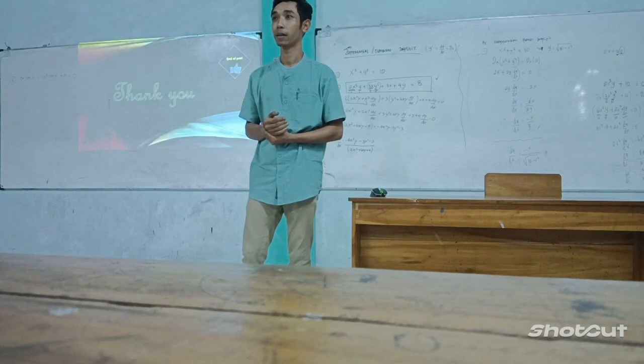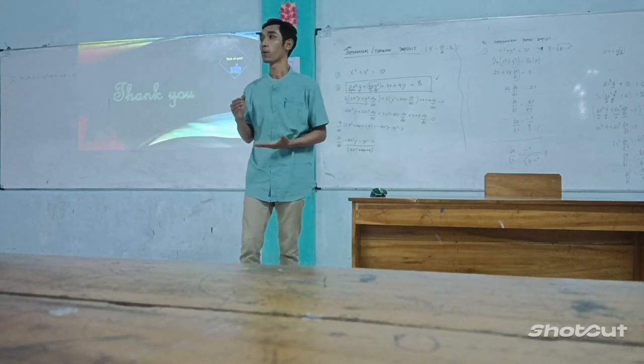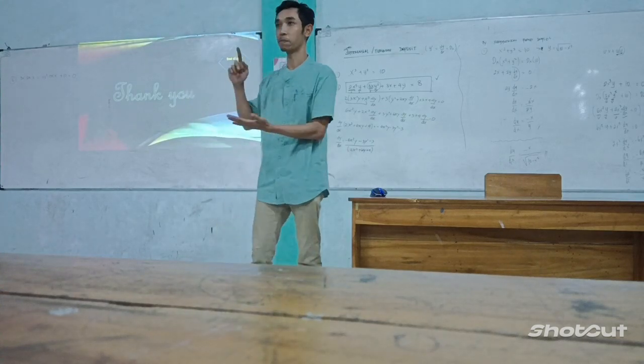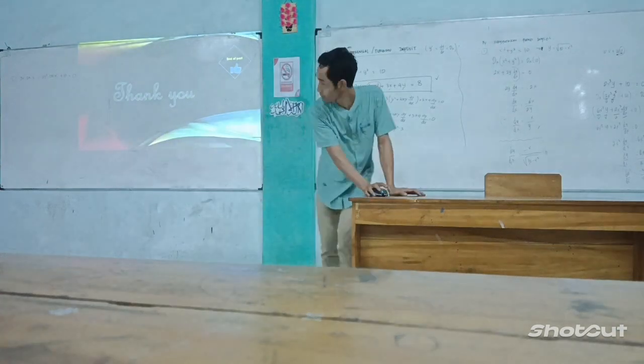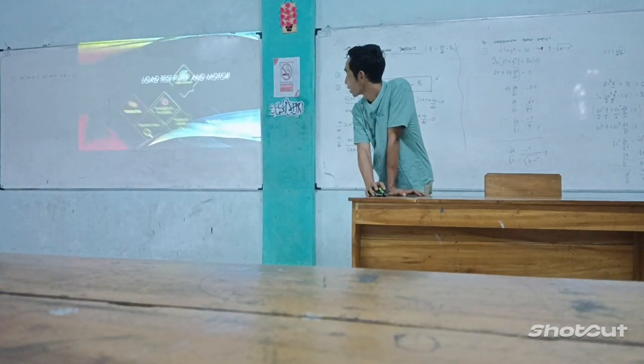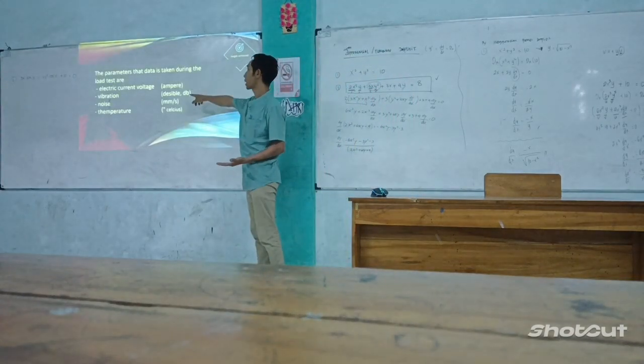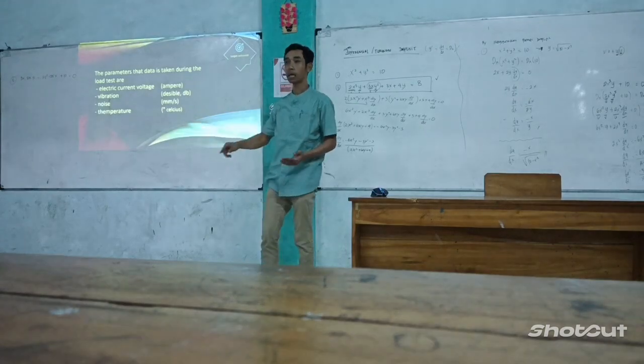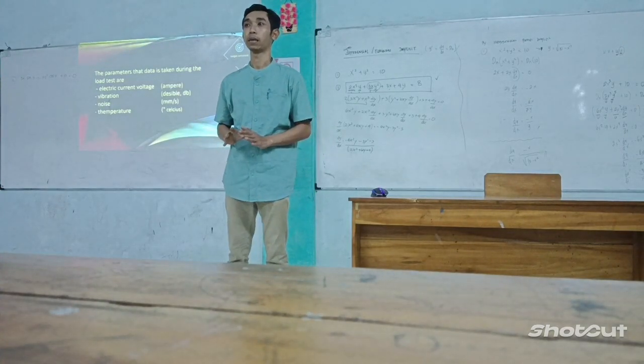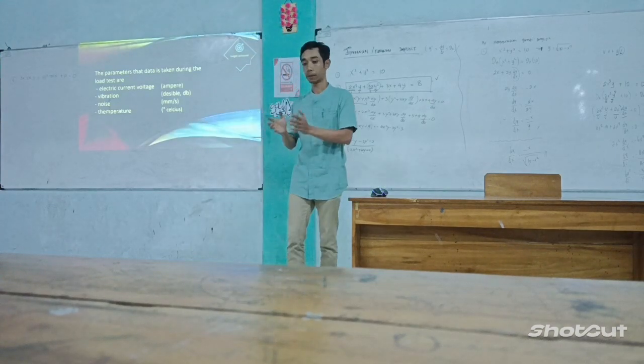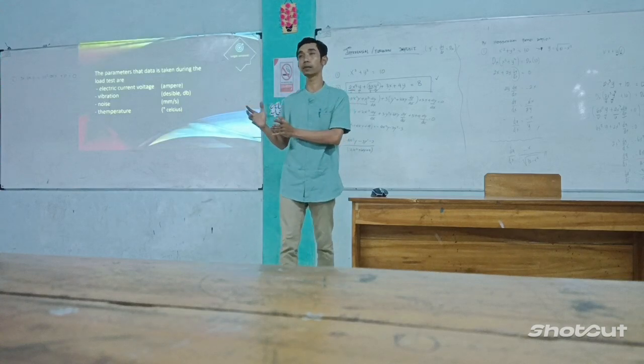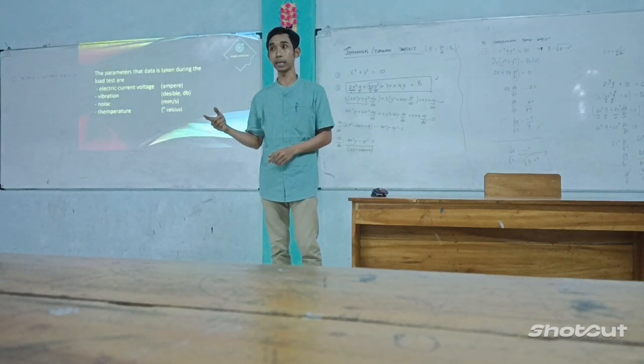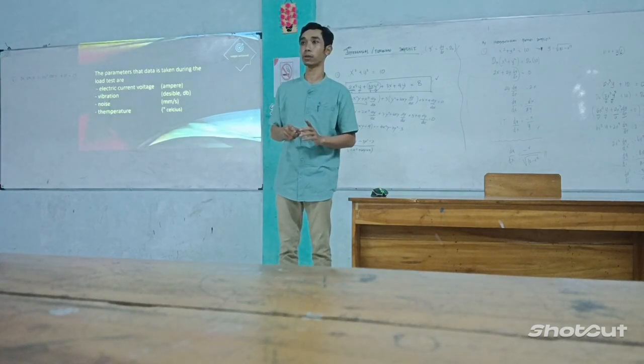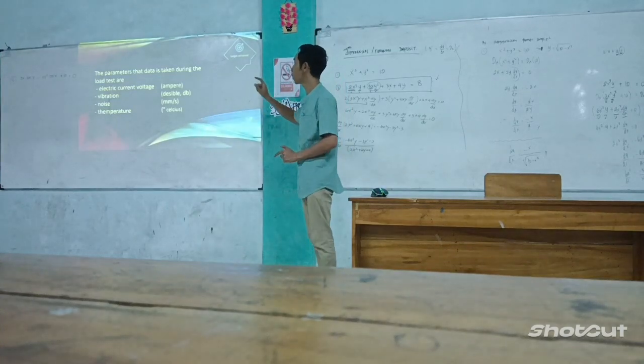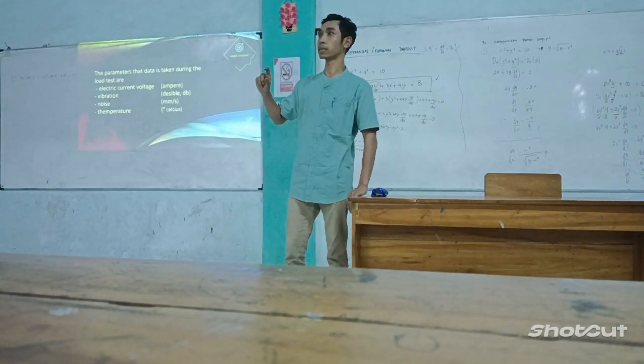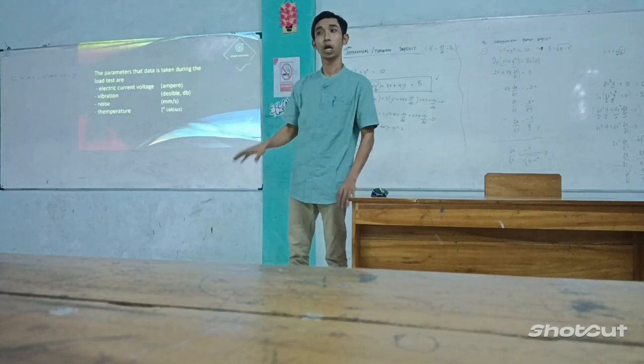Okay, thank you. The parameters of vibration, electric current voltage ampere, noise, and temperature are not the same for every equipment. For example, an electrical motor of 380 volts is different from one of 6 kilovolts. The parameter follows the equipment, it is not the same.